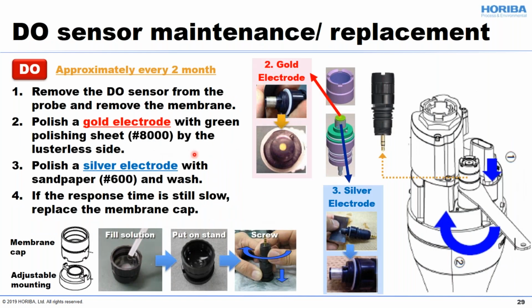This is how to replace the dissolved oxygen electrode. It's a little different from replacing the pH or ORP electrodes. The dissolved oxygen function uses an alkali solution inside, and the electrode is consumed by oxygen across the membrane. So first, you need to detach the old membrane and refresh the pore of the electrode by polishing it.